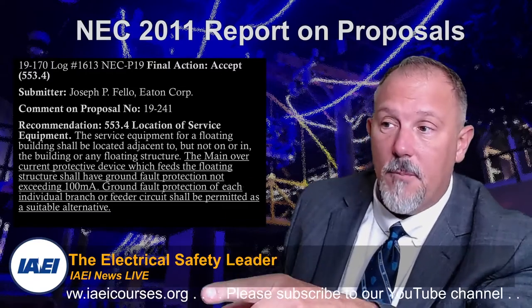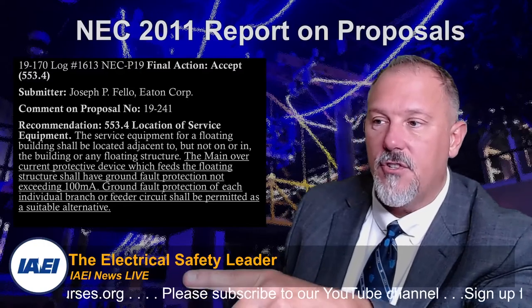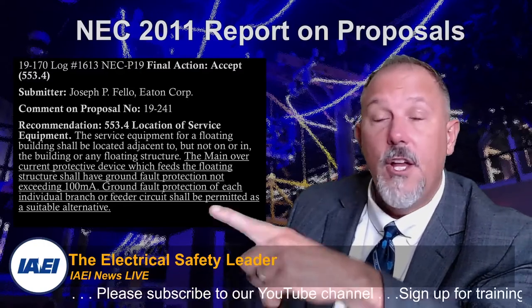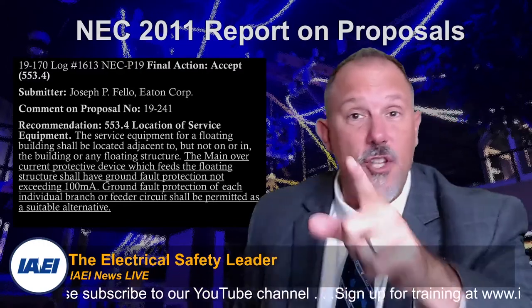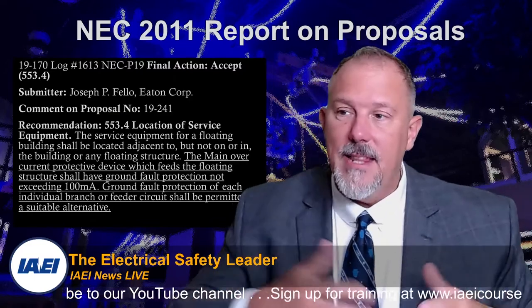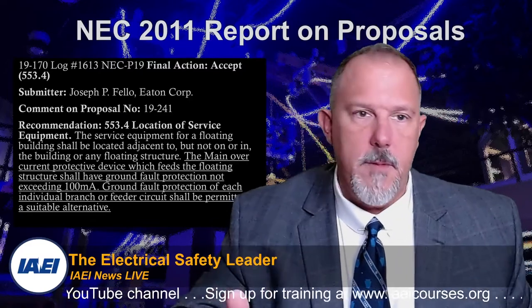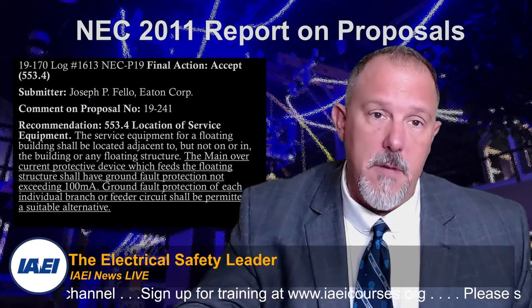And it says ground fault protection for each individual branch or feeder circuit shall be permitted as a suitable alternative. So you could have ground fault protection which is not GFCI. It's anything up to 100 milliamps, so it could be 30 milliamps, 60 milliamps, 50 milliamps.